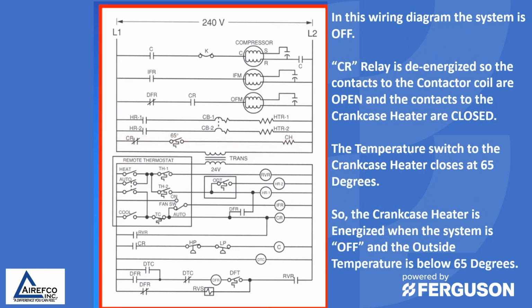In this wiring diagram, the system is off. The CR relay is de-energized, so the contacts to the contactor coil are open, and the contacts to the crankcase heater are closed. The temperature switch to the crankcase heater closes at 65 degrees. So the crankcase heater is energized when the system is off and the outside temperature is below 65 degrees.